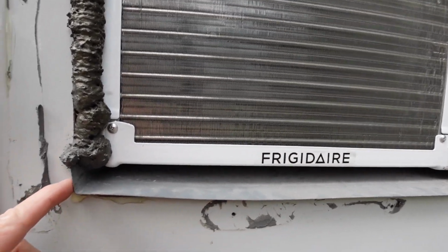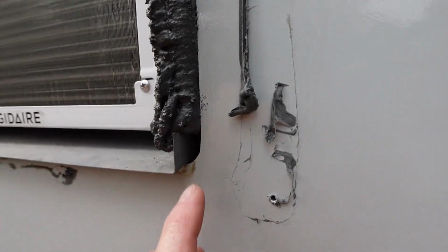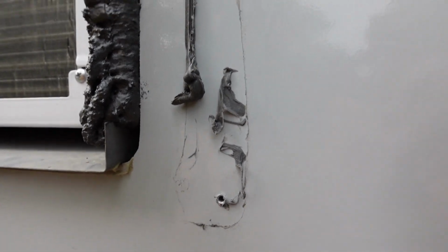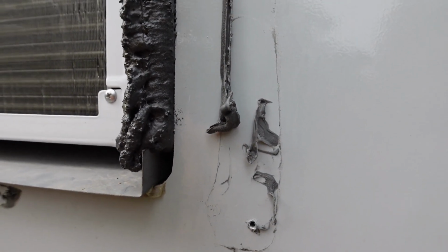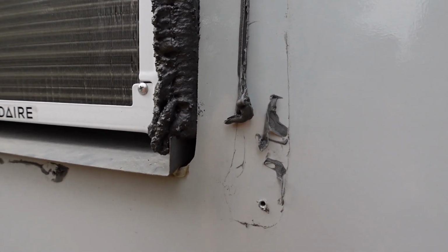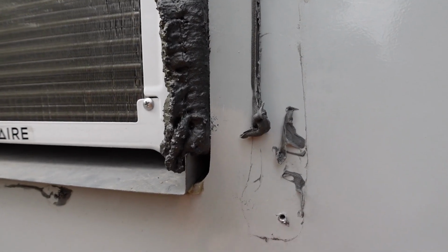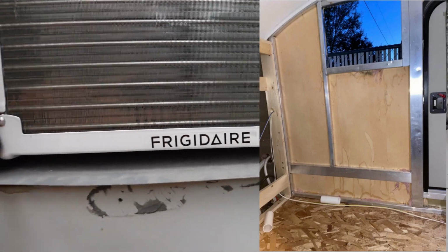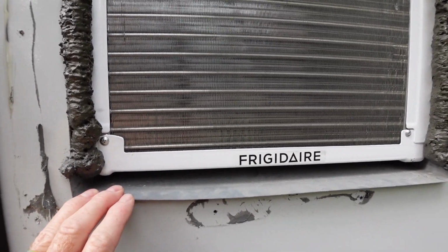Now, here in the corners, you can see in this corner here, and especially back here on this corner, they left some big gaping holes, and you can see all the way into the metal structure. You can see the shiny metal down inside there if I can get the right view. So those corners should have really been sealed up to keep water out, because once that water gets inside this wall right here and gets that insulation wet, it does real damage. I'll post pictures of that; a couple are posted on the Facebook page. But overall, I'm pleasantly surprised to see how well it is sealed up on the outside from a water standpoint.